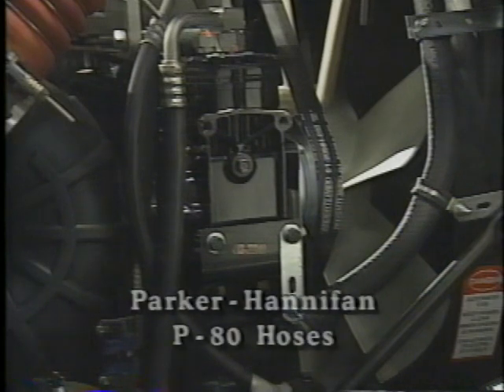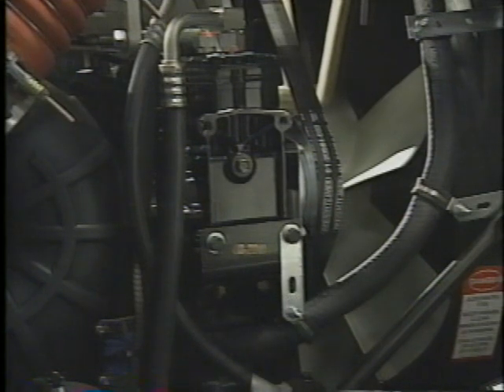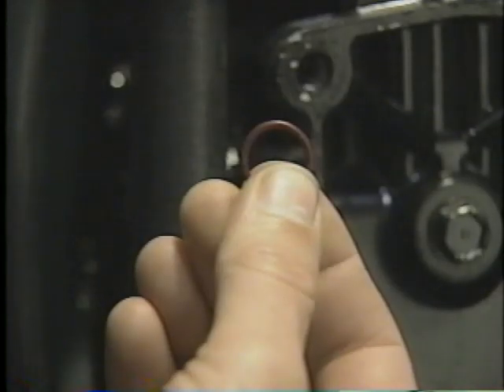The condenser looks the same, but is designed to be more efficient at removing heat from the refrigerant. The system hoses are the same Parker-Hannifin P80 hoses that Freightliner has used since 1988. The hose features a nylon barrier core to keep refrigerant in and moisture out. The neoprene O-rings are the same as those used with the R12 system. The O-ring color changed to red in 1992.